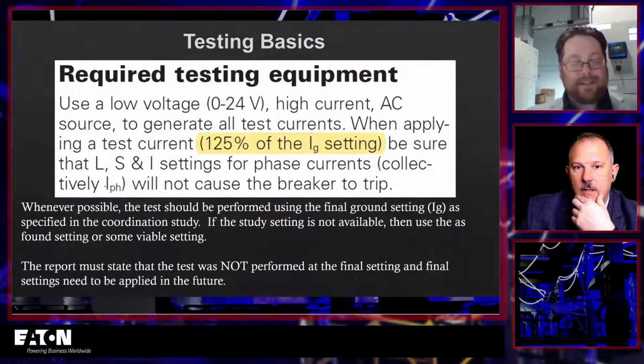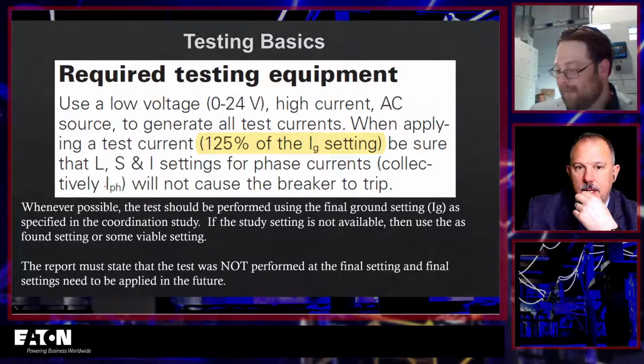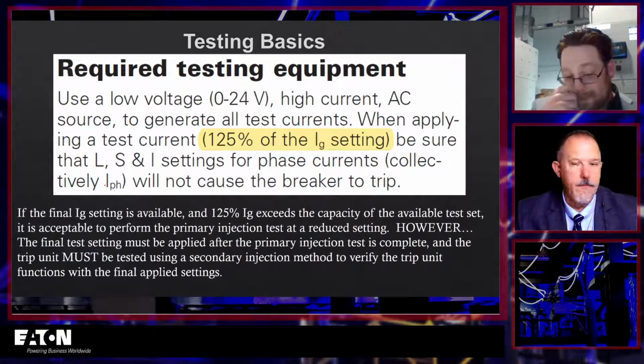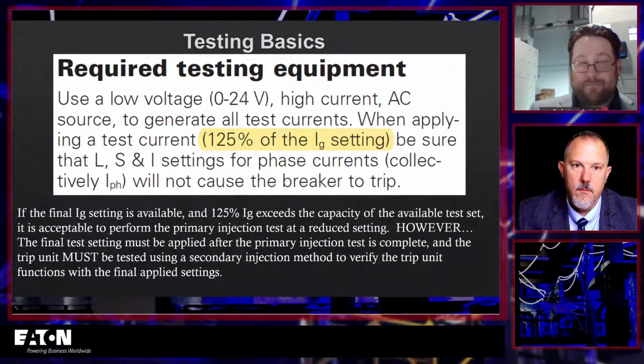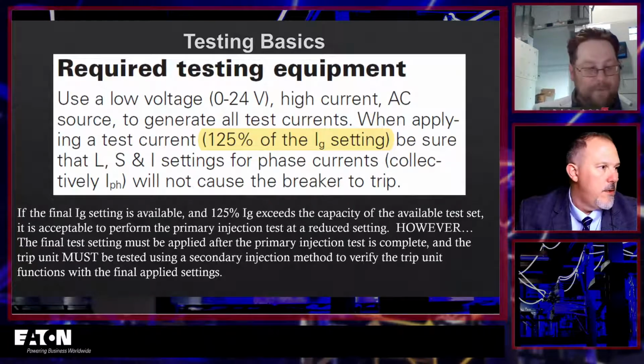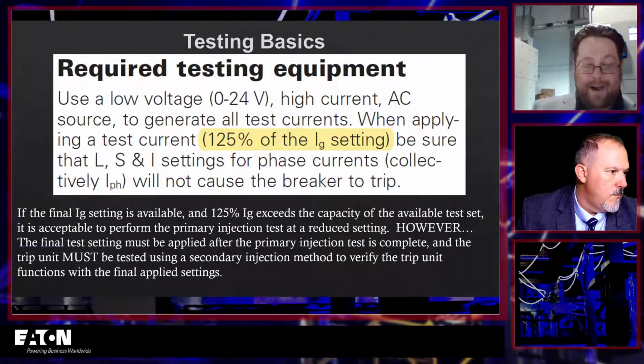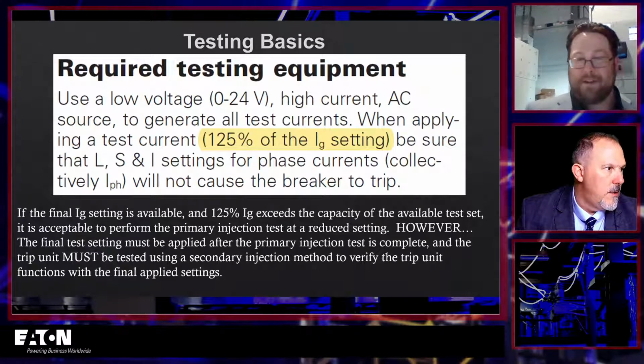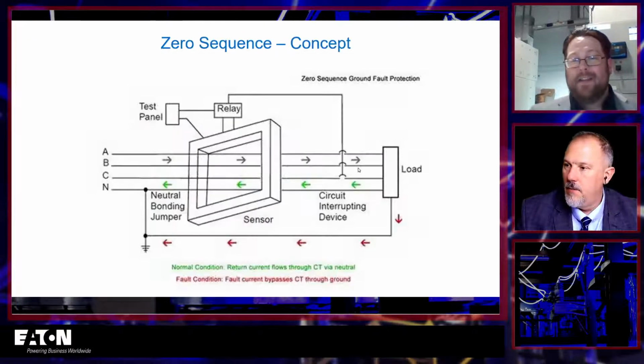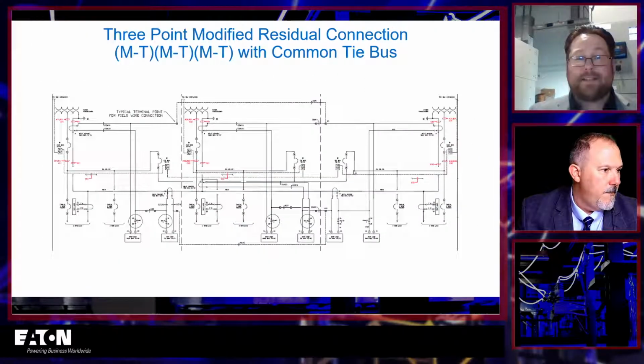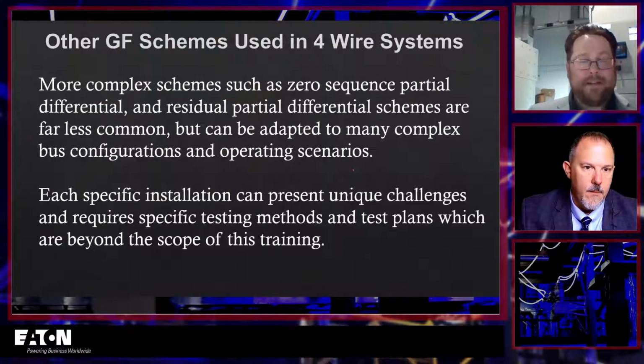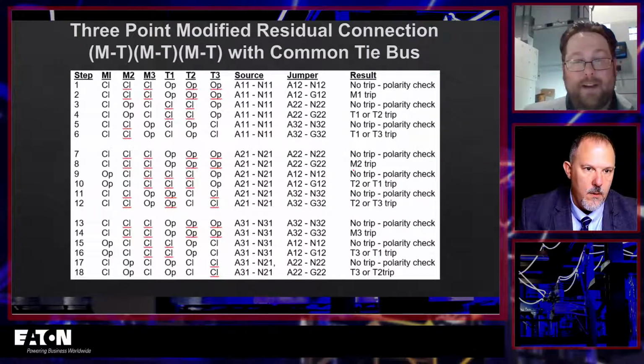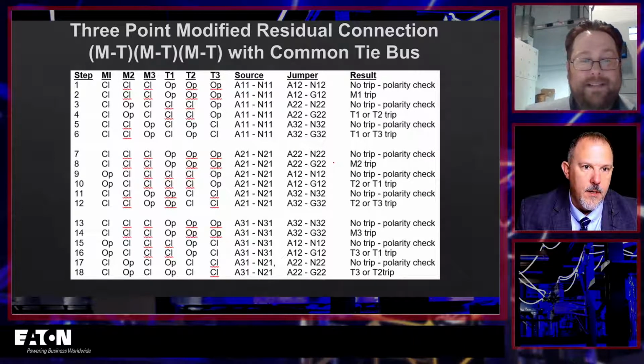So, talking about how complex this can be, I sent you that one slideshow. What happens if you have a residual connection? It's slide 50 in my slideshow, Tom. And you have that main-tie situation, right? So 3 mains and 3 ties. That is 18 tests that you're going to perform on this ground fault system. It's not necessarily a difficult topic to understand ultimately, but there's a lot of details to it. Yep, right there, 18 different tests to perform.